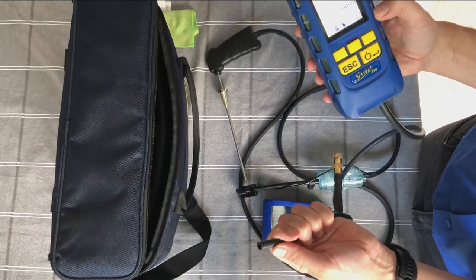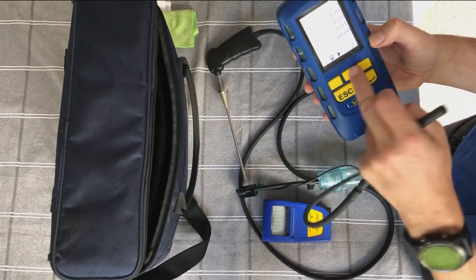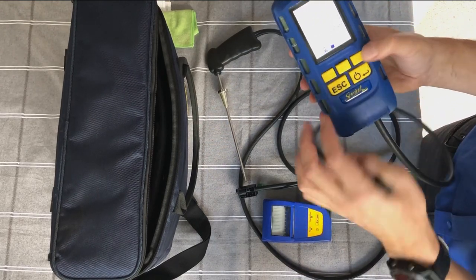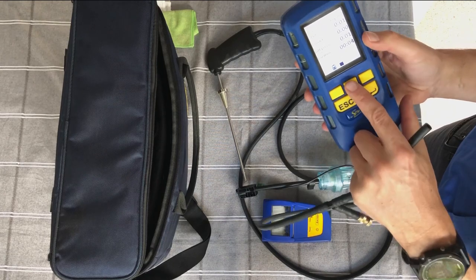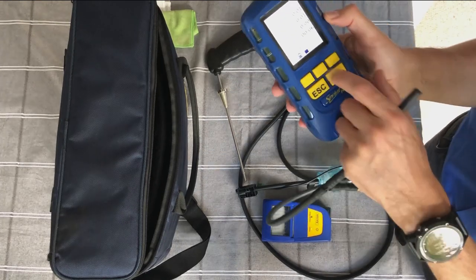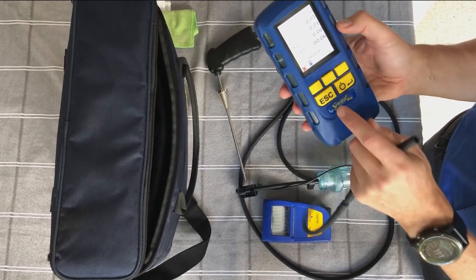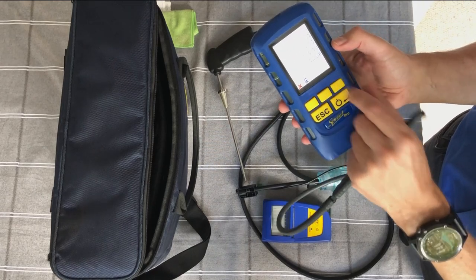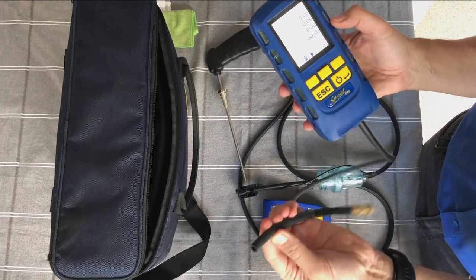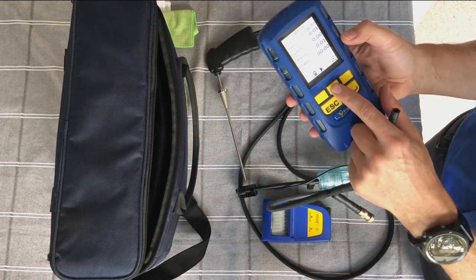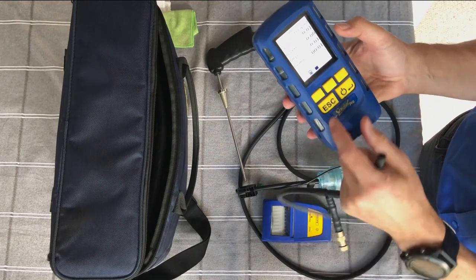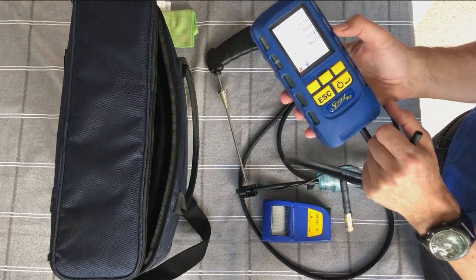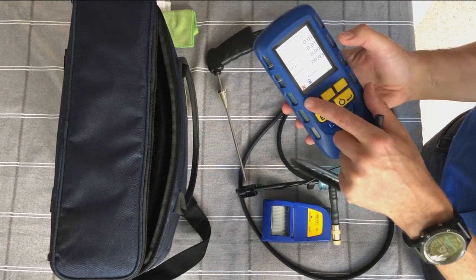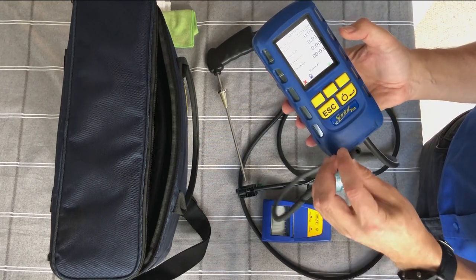It then allows you to set up for stabilisation. Again, press start when you're ready and stop when you're finished. I think it's another minute for stabilisation on domestic, isn't it? Again, I've only done 6 seconds, but you get the idea. I'm going to pass it because it was all fine. Then you can set up for your tightness test, hit start, a 2 minute test. At the end of that 2 minutes, you can stop. I'm going to fail it just to show, because obviously these were rubbish readings anyway.